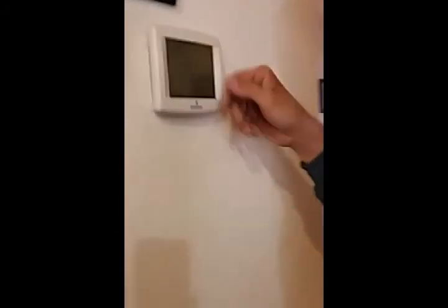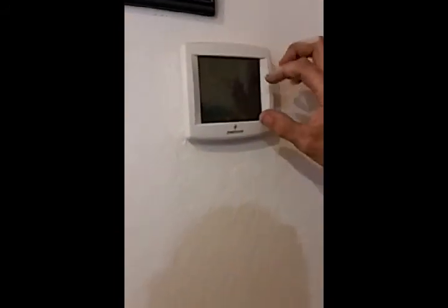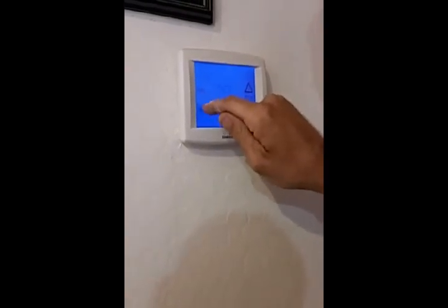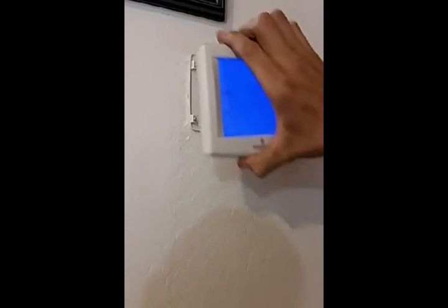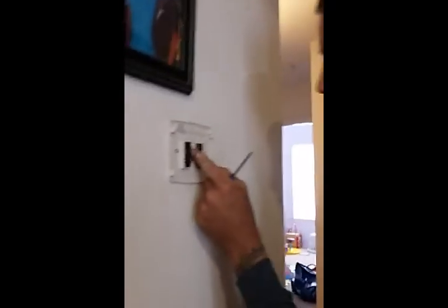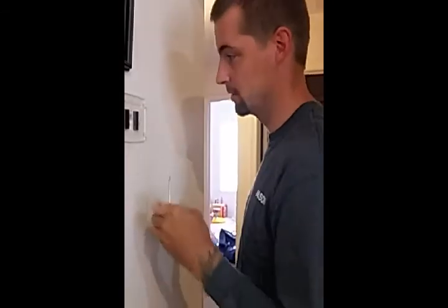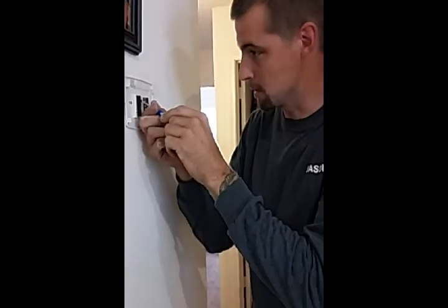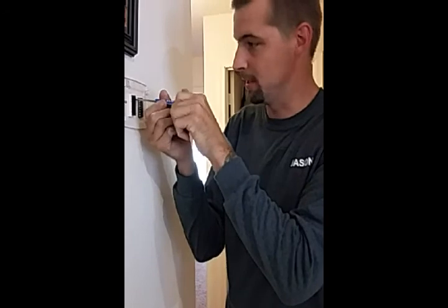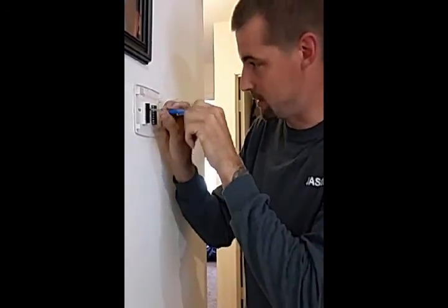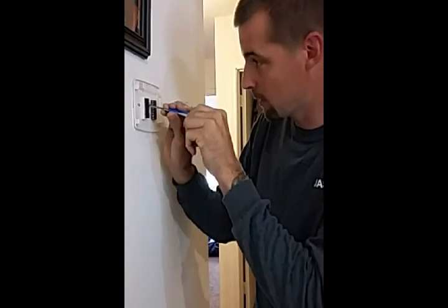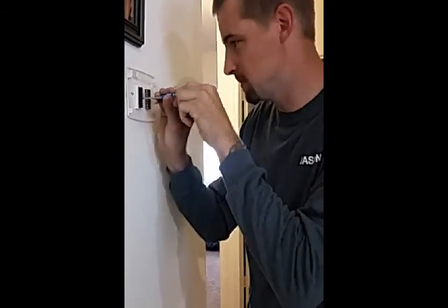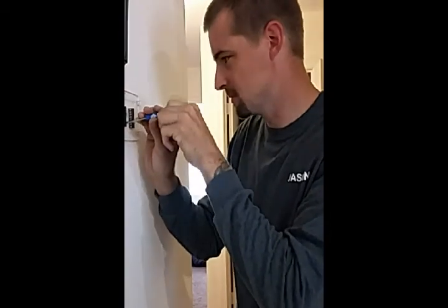Okay, the system's off right now. It's not off, but it's just not calling. Basically what I'm going to do is I'm going to switch it to the off position right now and pull the base off and make sure that all these electrical connections, low voltage connections, are all tight. Okay, sometimes they can work their way loose and cause shorts, and then your transformer will have to be replaced or re-fused. So we'll tighten these up here. Okay, all that is tight. So we'll go ahead and put this back on here.